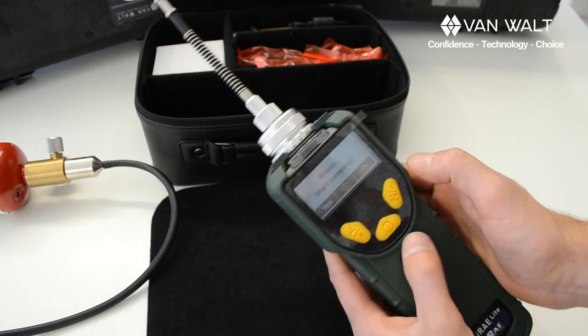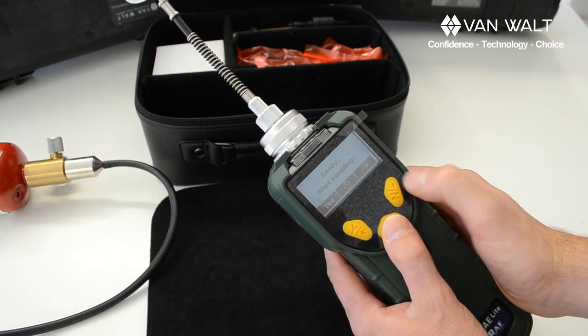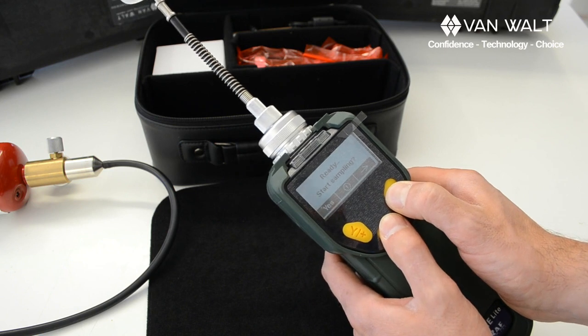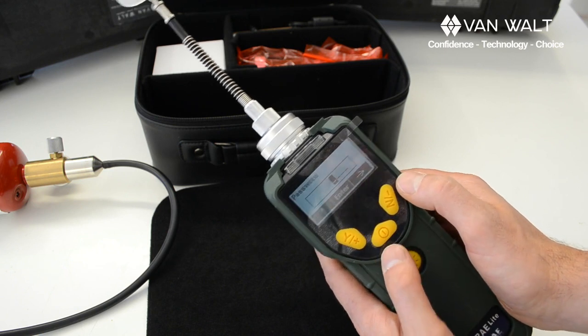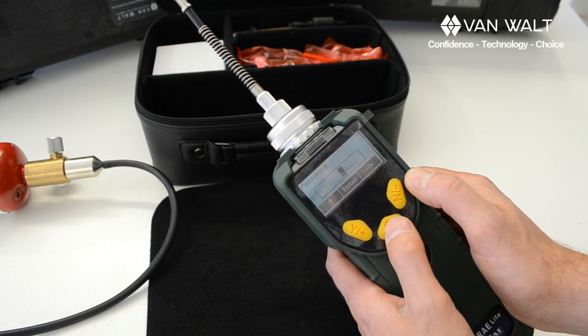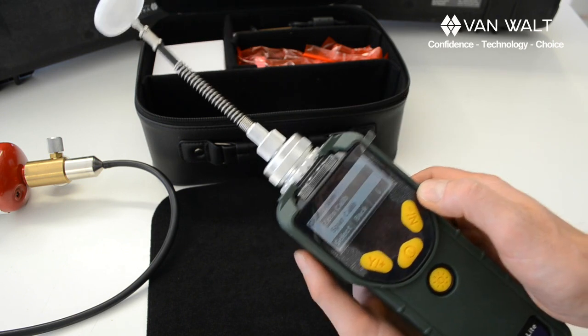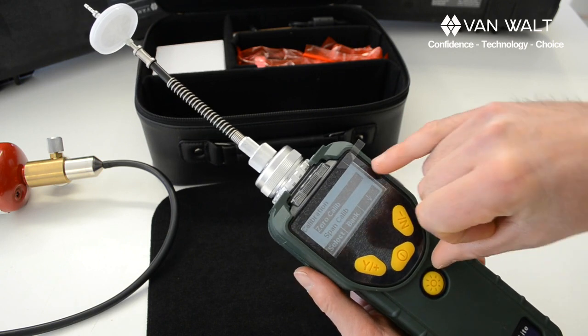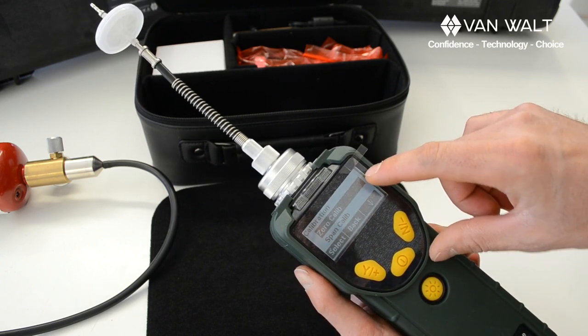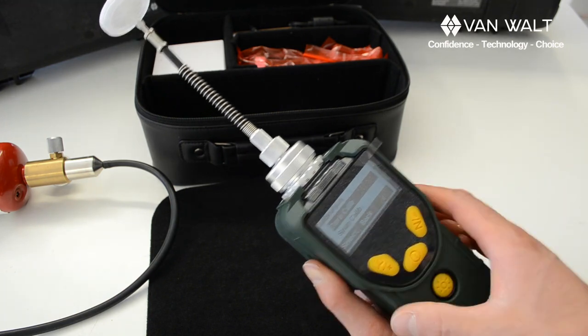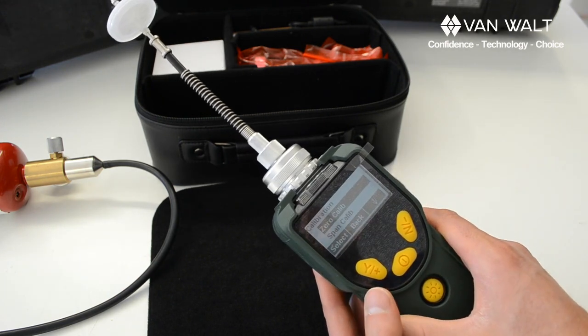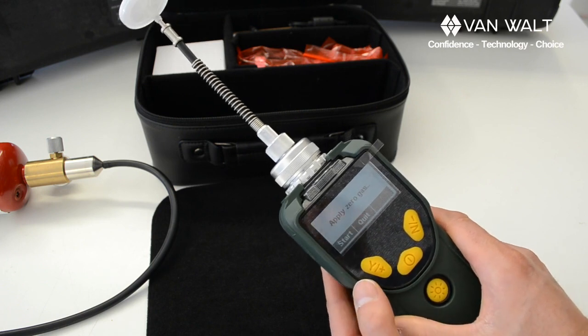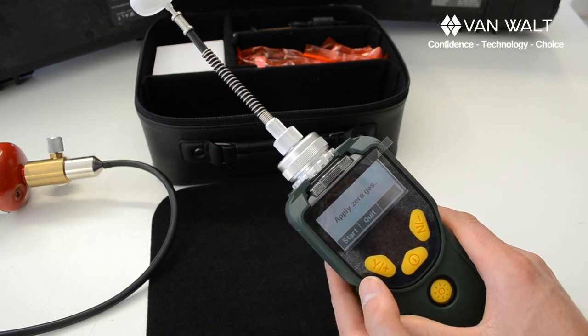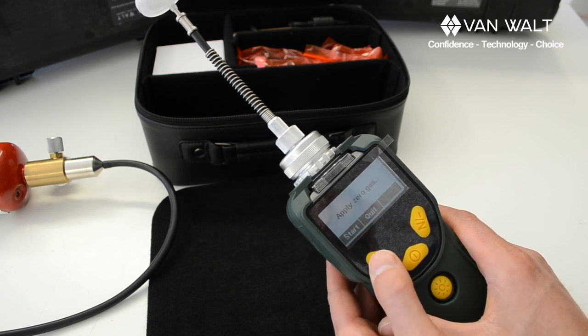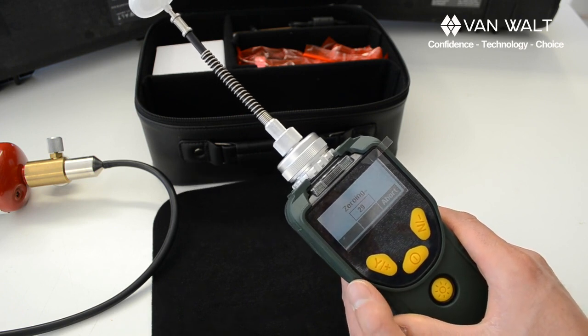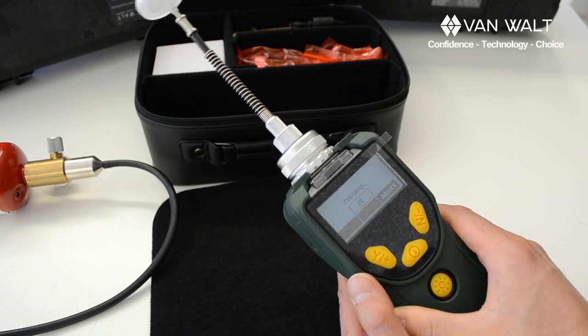No, what we're going to do now is press and hold the power and the right button. It asks for a password, ignore that, just press enter. And the pump started, and now it's giving us two options here. Well, it's actually saying give me 0, so we're in a fresh air environment. Obviously be careful to make sure that you are in a fresh air environment. I'm going to select that. Apply 0 gas. Well, we haven't got a 0 gas, we've just got a known fresh environment. Start, and that will take 30 seconds to zero.